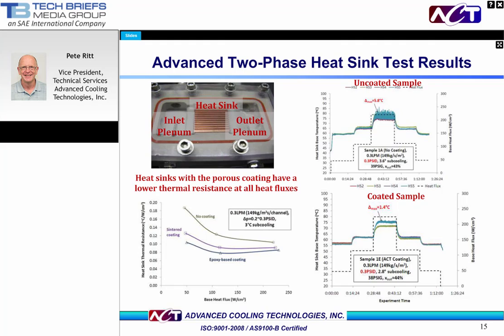Here is a summary of the test results. The test system is seen on the upper left. 3 samples were tested: a bare copper mini-channel cooler, a sintered powder microporous coated one, and an epoxied microporous coated sample. The results of the 2 coatings were similar. In the graph on the lower left, thermal resistance is plotted at different base heat fluxes. As you can see, the coated samples showed lower thermal resistances at all heat fluxes tested.